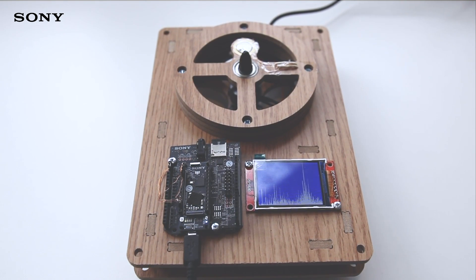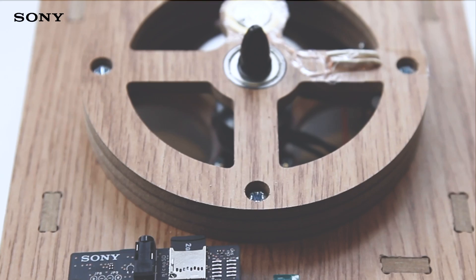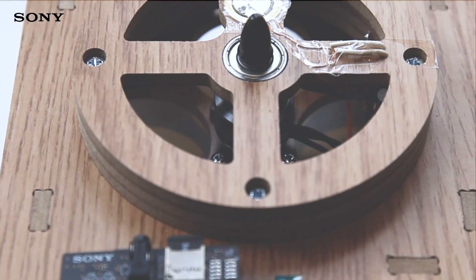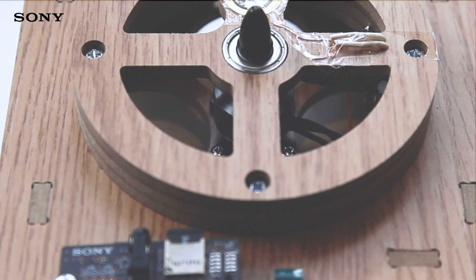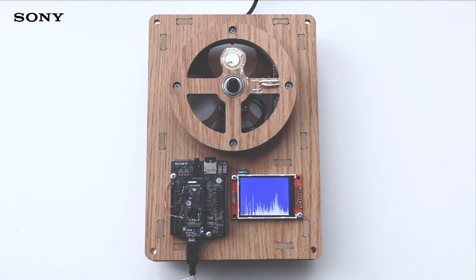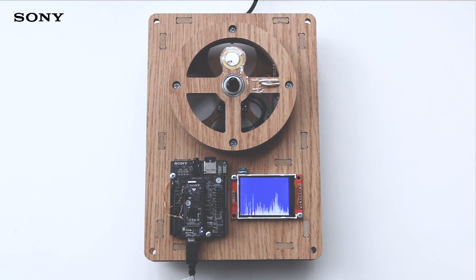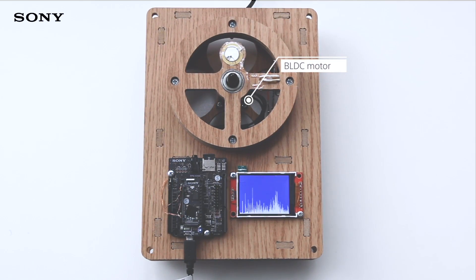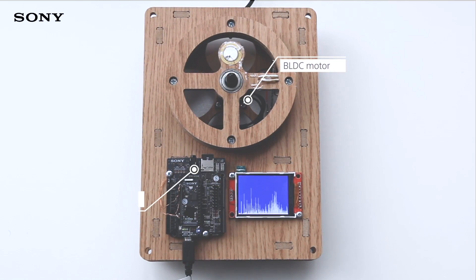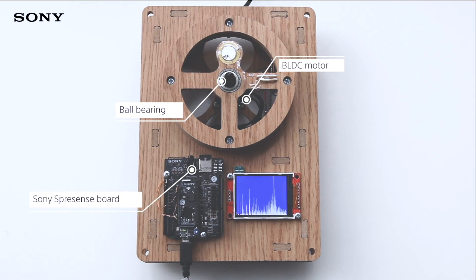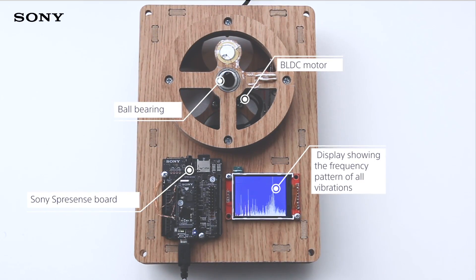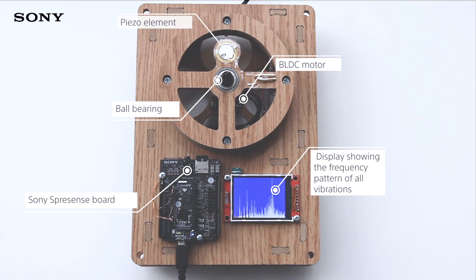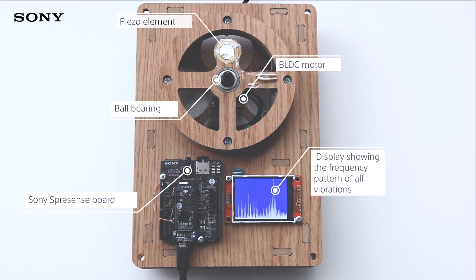This video will show you how to use the Spresense microcontroller board from Sony to continuously analyze the status of the bearings in industrial equipment in real-time. This simplified rig conceptually represents a typical piece of factory machinery with rotating parts supported by bearings. To monitor and analyze the condition of the bearings, a piezo element detects the vibration frequency pattern.